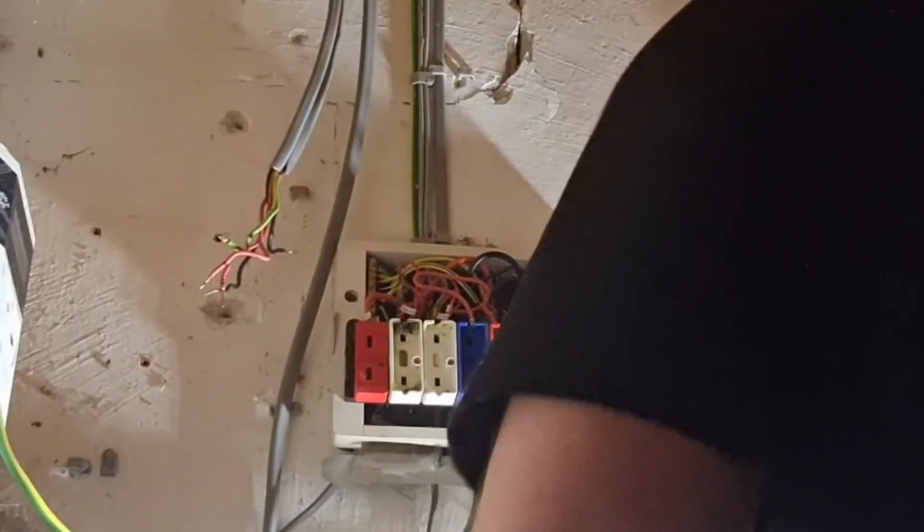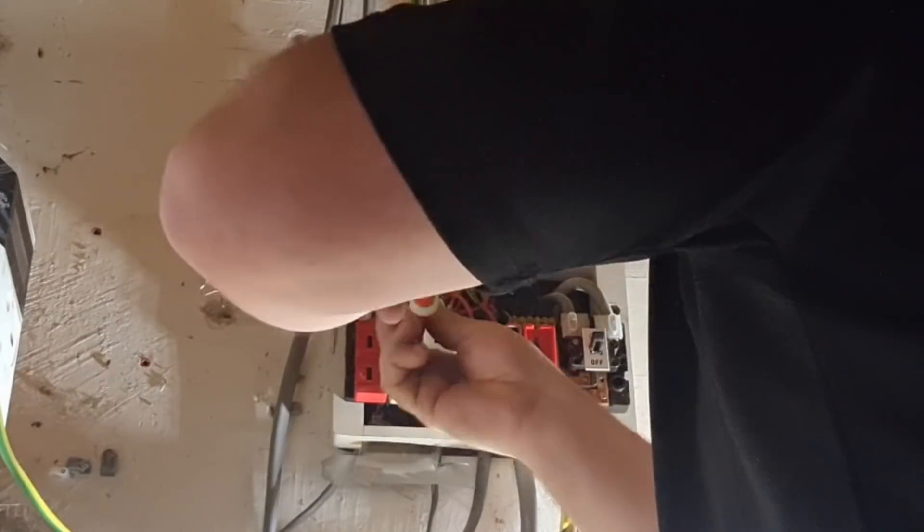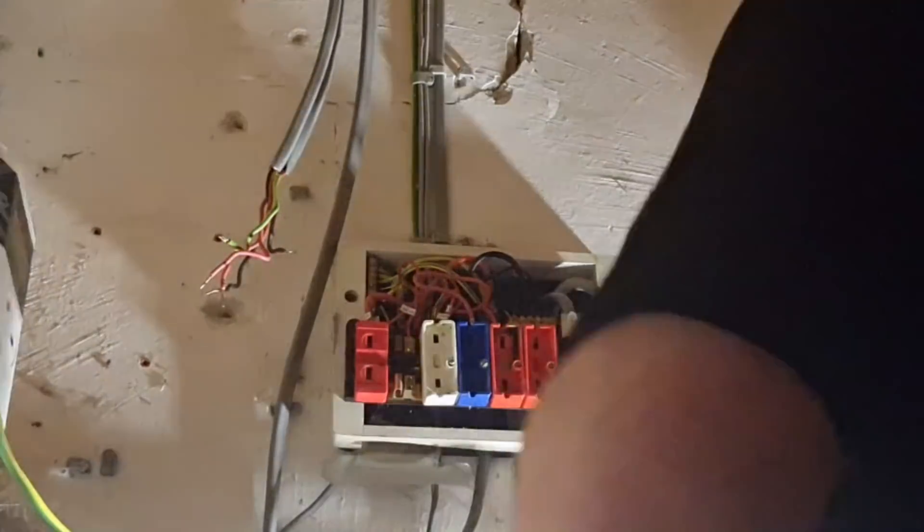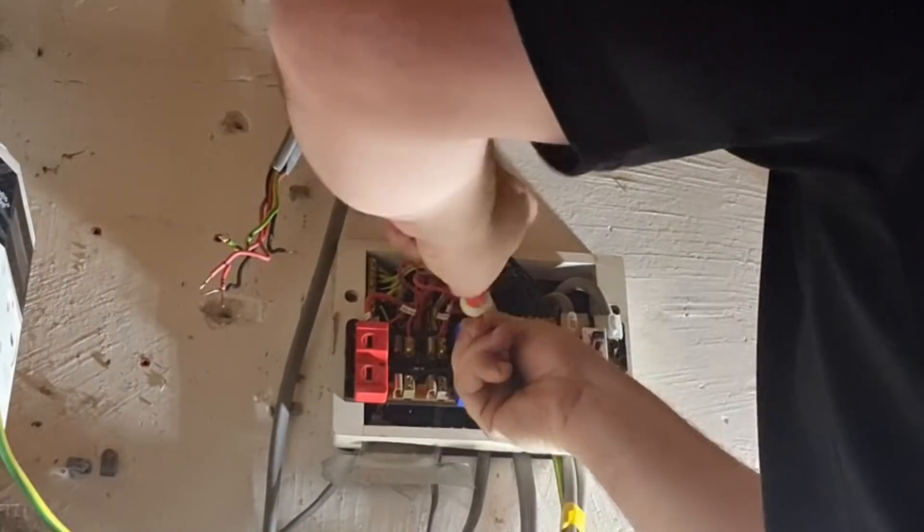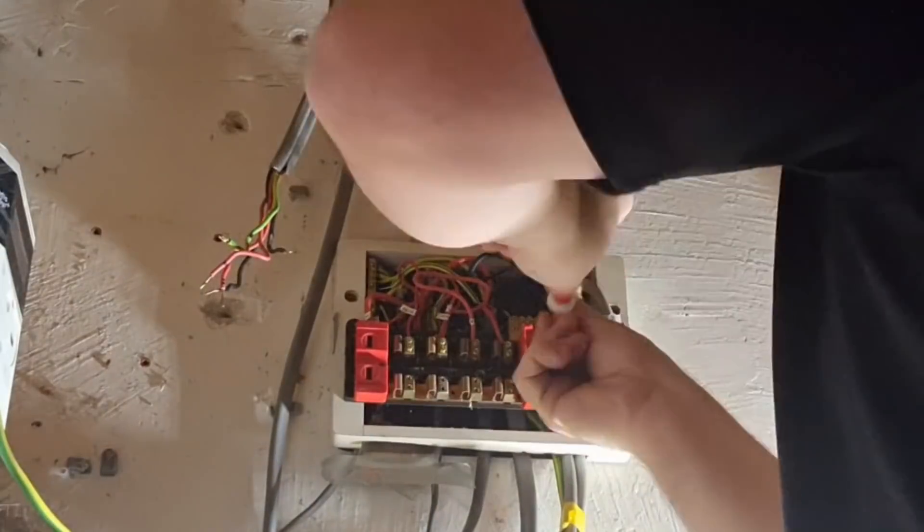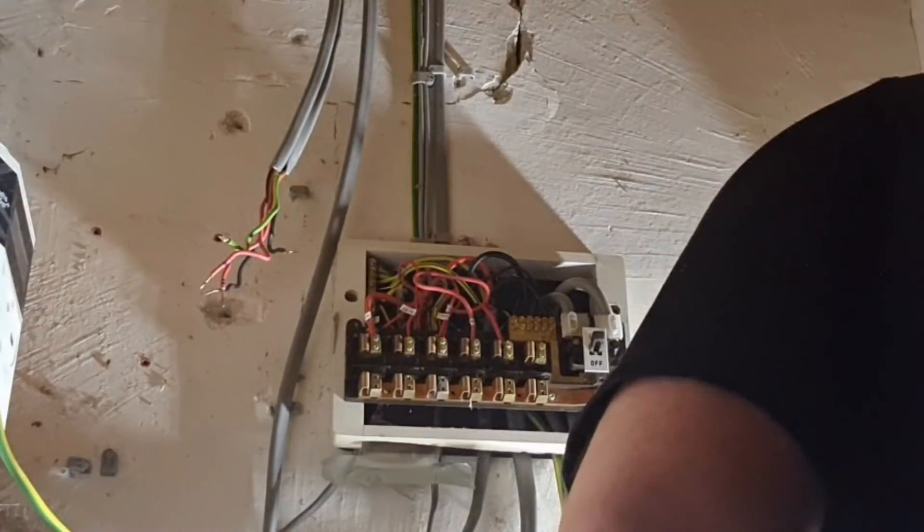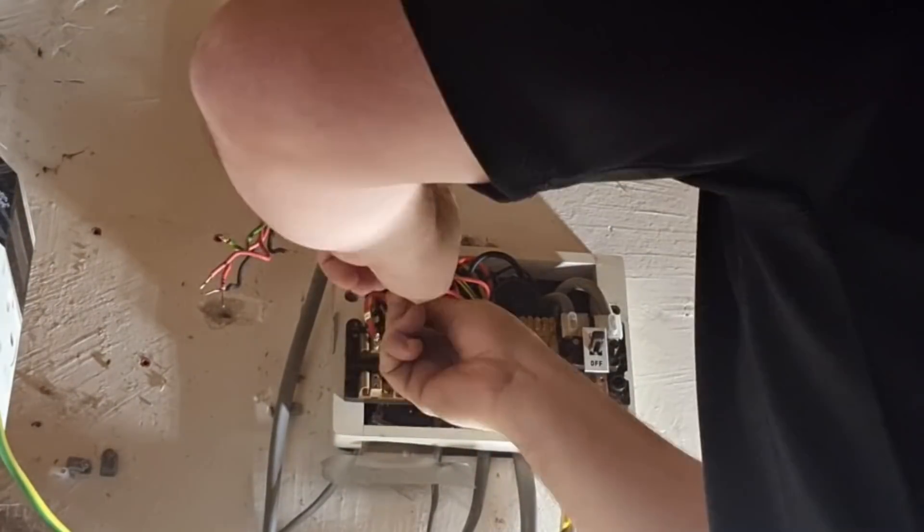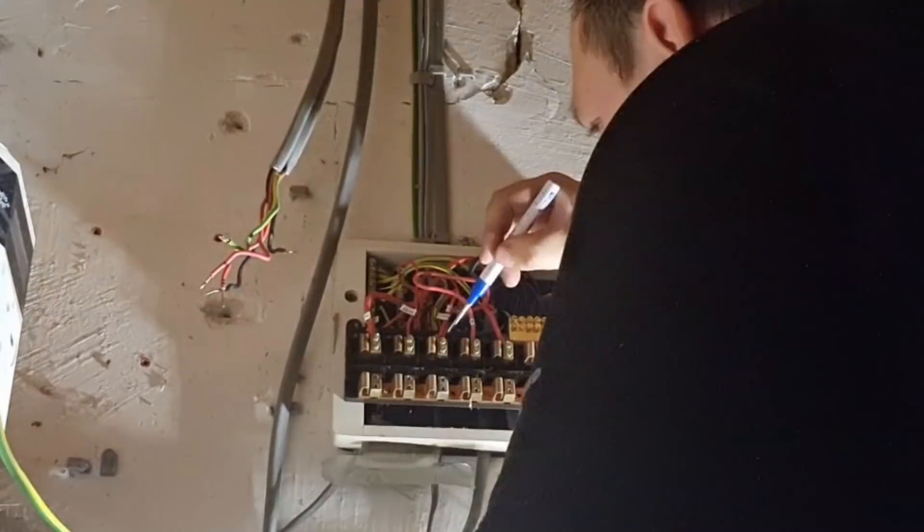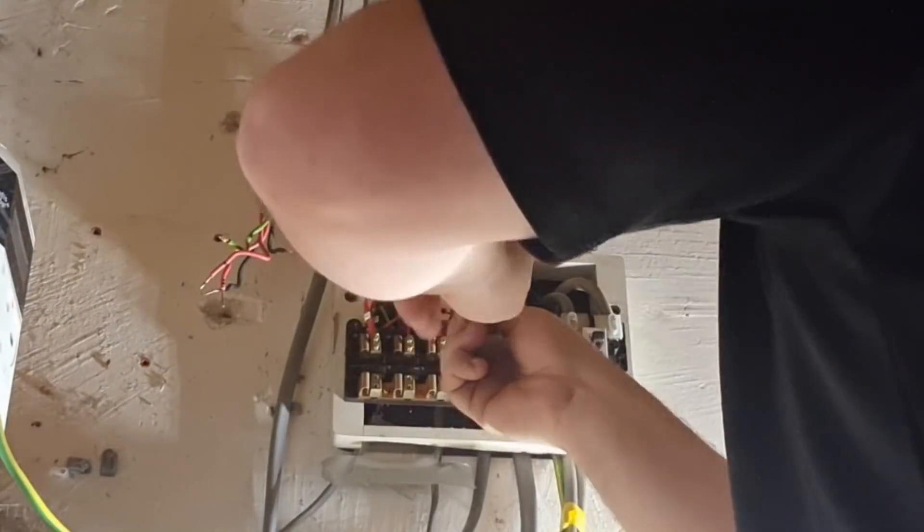This is a wooden backed one. Somebody put some gaffer tape on the front, it was actually cracked, so this needed to come out. You can see when we've done the test we've got the cables all marked up there just to help us out a little bit at this stage. So this again is PVC cable, it's all in pretty good nick actually to be truthful.